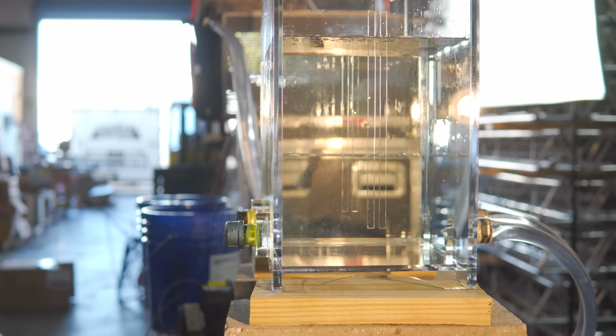Chad tells me that this fluid has tiny molecules, even tinier than water, so this coolant will find a leak if there is one. That said, we had the system filled up, we turned it on, and very quickly found a leak. Whoa! Okay, stop.